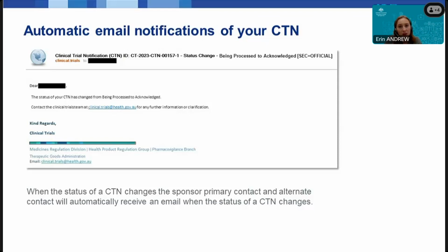One question we are often asked is, when is the CTN officially notified and when can you start supplying the goods to clinical trial patients? Well, as per the therapeutic goods regulations and the therapeutic goods medical device regulations, a clinical trial is deemed notified once the CTN form has been submitted with payment of the relevant fee to the TGA. Once this occurs, the exemption under the Therapeutic Goods Act comes into effect. We check that the CTN form has been completed correctly and the relevant fee has been paid during the being processed phase. As such, most sponsors prefer to wait until they have received the acknowledged status to be confident that the exemption under the Therapeutic Goods Act is in effect.